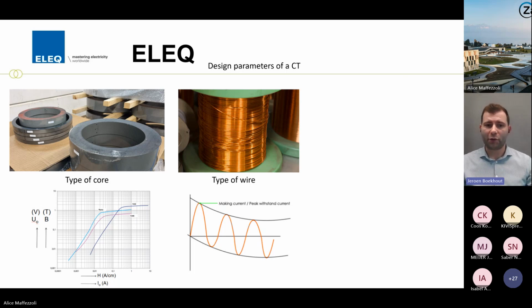There's an impact on the positioning of the winding, because partial winding can lead to partial saturation and can also lead to early saturation of the core. So it's not only the winding, the wire size, but also the positioning of the winding on the core. The optimal way to wind is to evenly distribute on a round core without air gaps. That usually gives the best and most stable result, independent of the position of the primary winding, because the position of the primary winding within the CT can be influenced if it's not evenly wound.